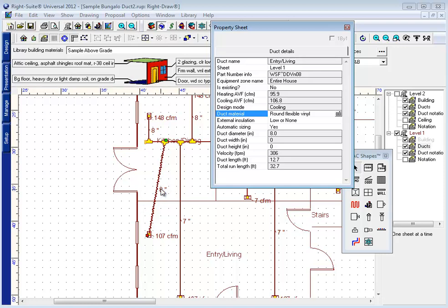Note that the size of the duct changed automatically to account for the higher coefficient of friction, and that the icon that we use for the duct became a squiggly line designating a flex duct.